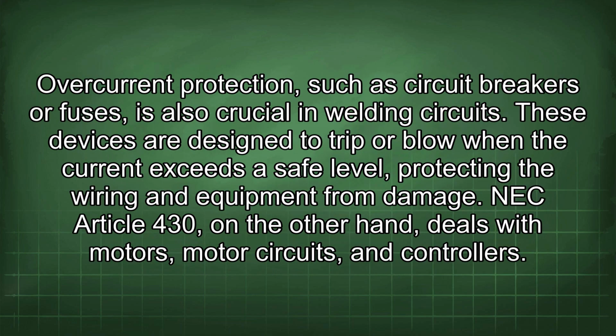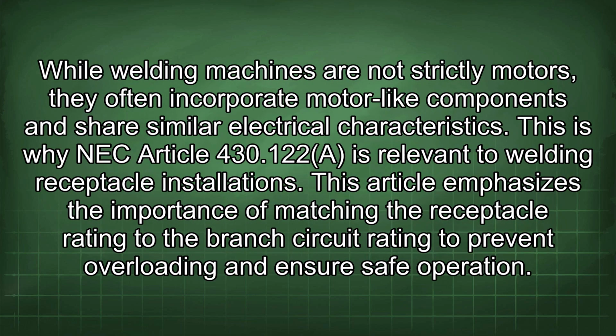Overcurrent protection, such as circuit breakers or fuses, is also crucial in welding circuits. These devices are designed to trip or blow when the current exceeds a safe level, protecting the wiring and equipment from damage. NEC Article 430, on the other hand, deals with motors, motor circuits, and controllers. While welding machines are not strictly motors, they often incorporate motor-like components and share similar electrical characteristics. This is why NEC Article 430.122 is relevant to welding receptacle installations. This article emphasizes the importance of matching the receptacle rating to the branch circuit rating to prevent overloading and ensure safe operation.